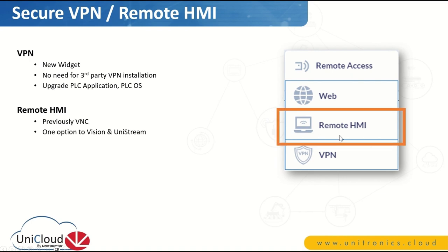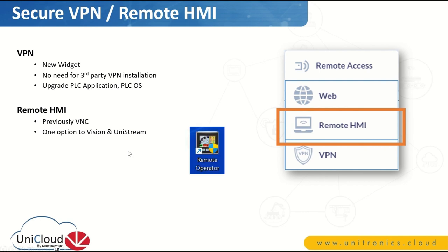The second enhancement under the remote access category is Remote HMI. Previously it was called VNC, but now it's an enhanced functionality that enables remote access to both Vision and Unistream PLCs. UniCloud will know automatically what type of PLC you want to connect to. In the case of Unistream, it will enable and open a VNC window, and in the case of Vision, it will open your remote operator application installed on your computer. It's a seamless connection — you just click and the remote access connection is done automatically.